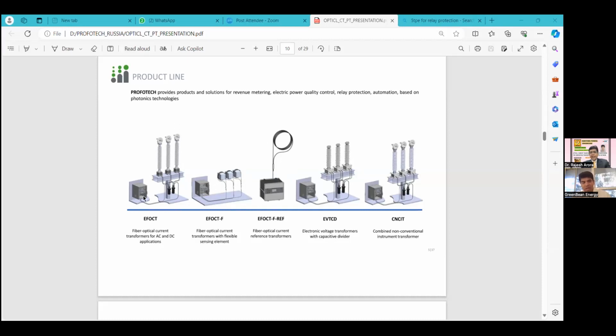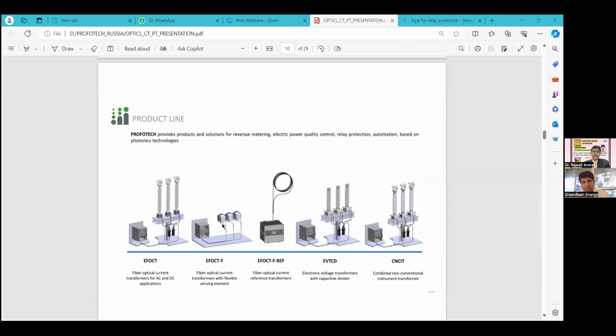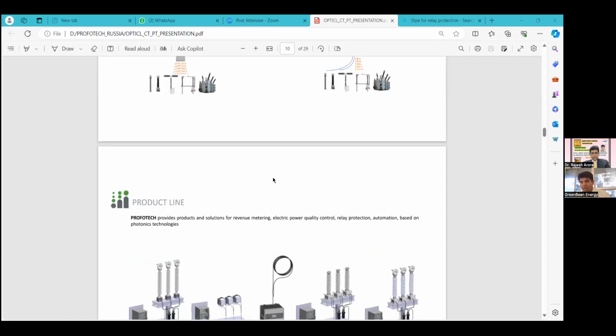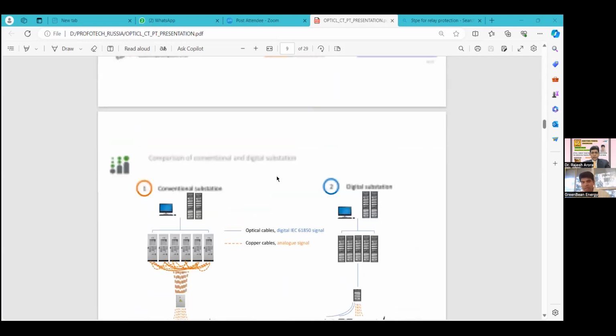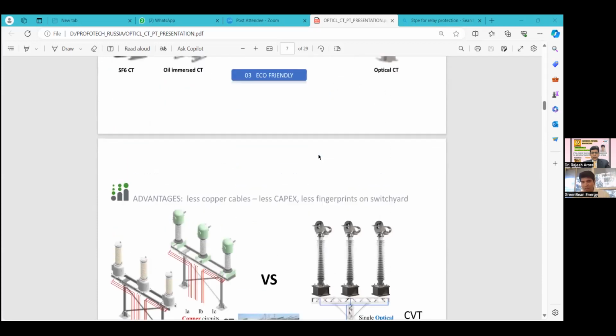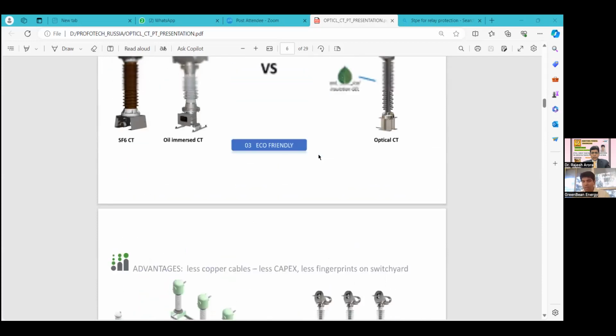I have understood the product, but I just want to understand the fundamental principle, how it can measure both AC as well as DC. The thing is that the sensing element is common for both. Okay, sir. There is no change in the sensing element design. Only the design will change with respect to the current rating and voltage class. So the design is changed, meaning the number of windings changes according to the voltage and current requirement.